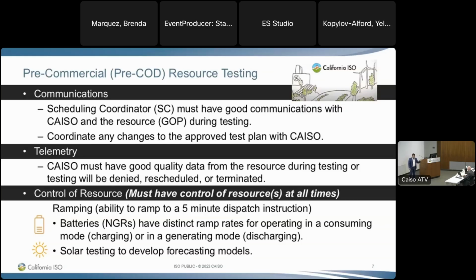Yeah, so the BPM for metering kind of highlights those critical points. There is a list of those critical points in the metering for BPM. For operations, really it comes down to three main values, but again you've got to look at that full list for sure. For visibility for us in the control room, good UPMW, UGMW, and a good UCON status, either open or closed. Those are the three critical ones, but there's a list in the BPM metering that talks about all the different items that we would need. So yeah, for us, for visibility for an operator, those are the three that we need to see at any given point in time.